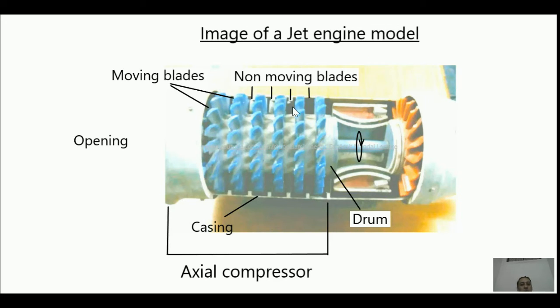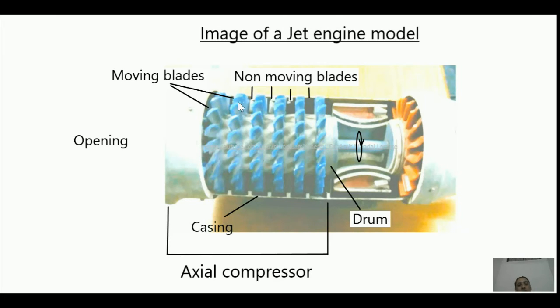Between two sets of moving blades there is a blank space where non-moving blades are installed. You can see these white-colored entities — they are non-moving blades attached to the casing, so they don't move. Their job is to raise the pressure: when fluid leaves the moving blades with high kinetic energy, it passes through these non-moving blades where pressure is raised. They also provide the proper direction to the air before it arrives at the next set of moving blades. One moving blade system plus one non-moving blade system equals one stage.